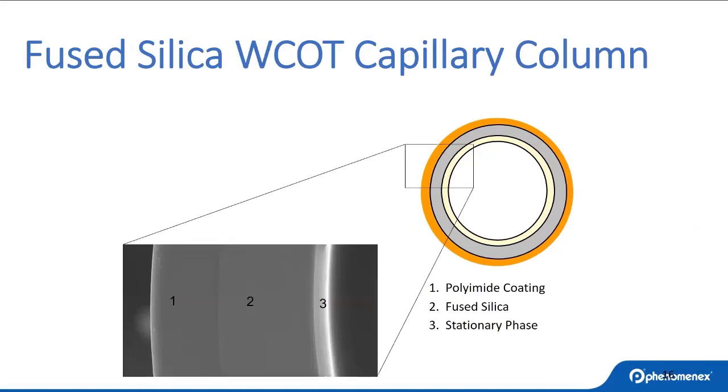Before we go further, let's look at a GC column. Here is a GC column cross-section. There are three specific layers within a capillary wall-coated GC column. The outermost layer is polyimide, which gives flexibility and temperature stability. The middle layer is fused silica — a pure glass that must be deactivated. The type of deactivation in that second layer dictates the sharpness of your peaks and helps reduce breakdown of active analytes. The third part is your stationary phase — a uniform stationary phase with adequate selectivity is going to help you get better separation.